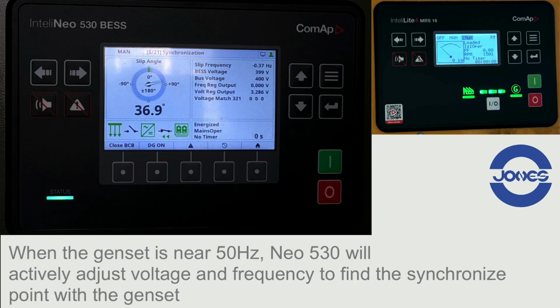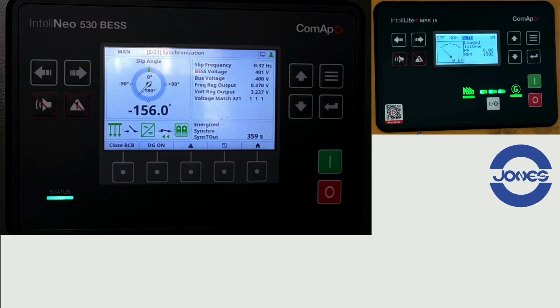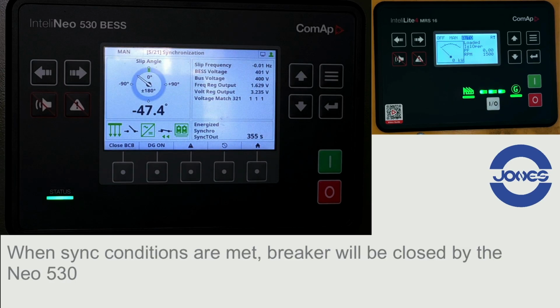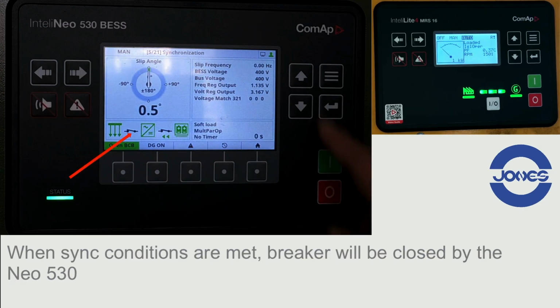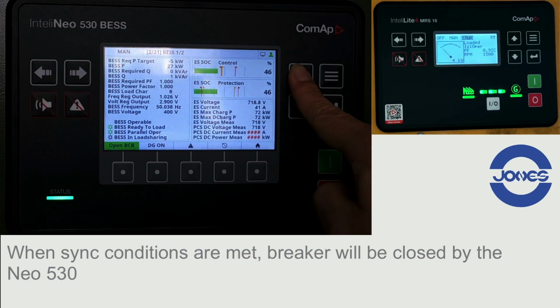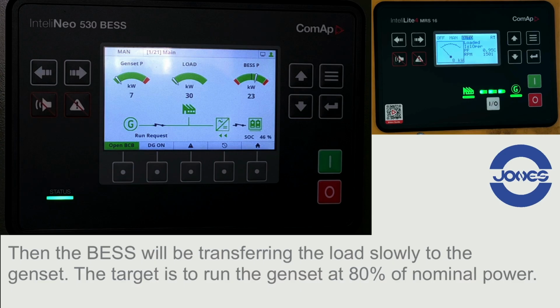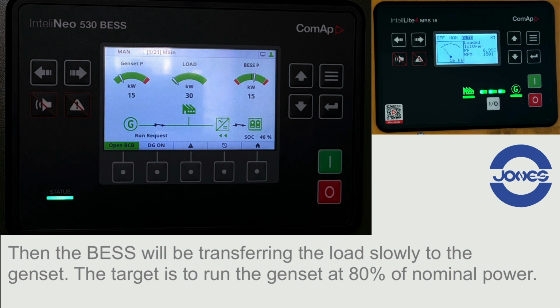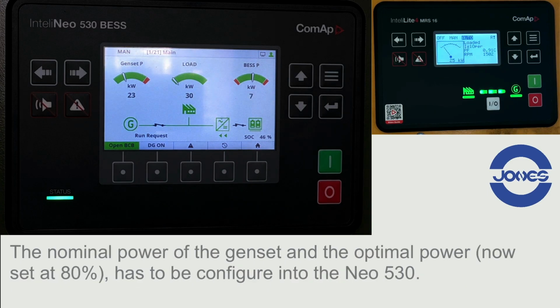When the genset is near 50 Hz, the Neo 530 will actively adjust the voltage and frequency to find the synchronous point with the genset. When sync conditions are met, the breaker will be closed by the Neo 530. Then the BESS will be transferring the load slowly to the genset. The target is to run the genset at 80% nominal power. The nominal power of the genset and the optimal power level, which is now set at 80%, has to be configured into the Neo 530.